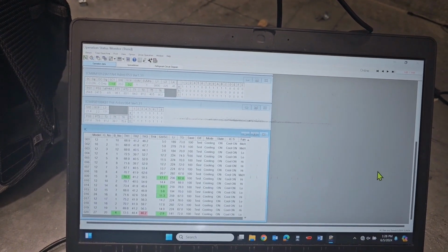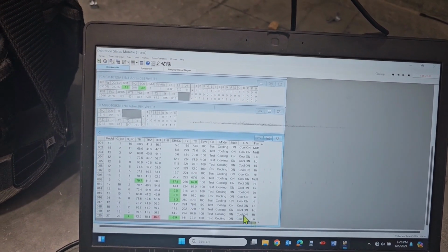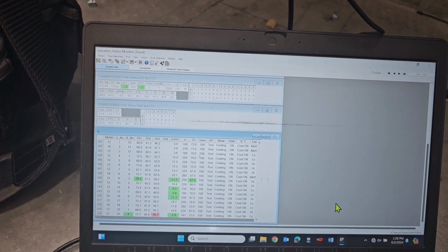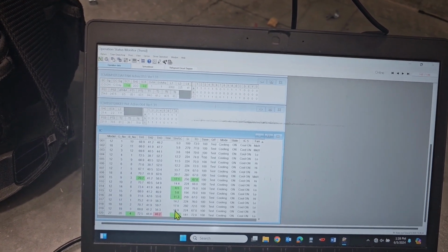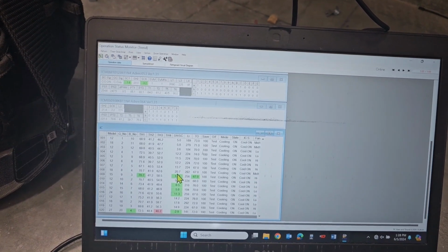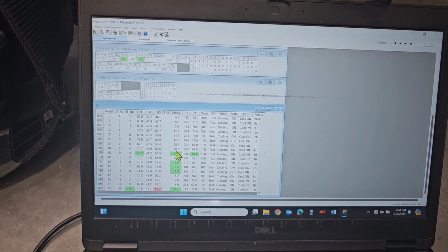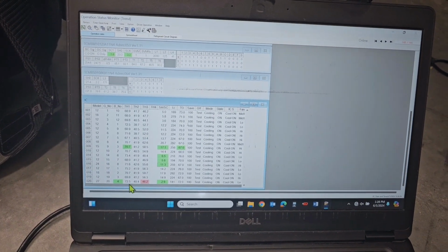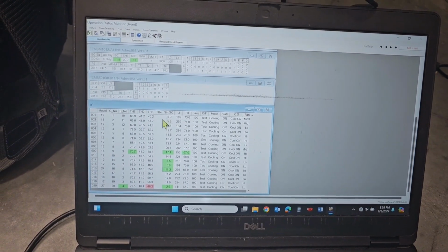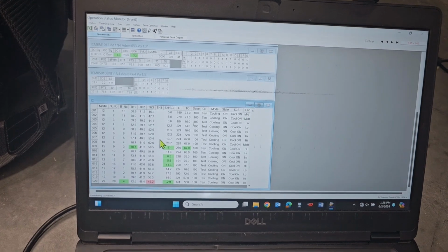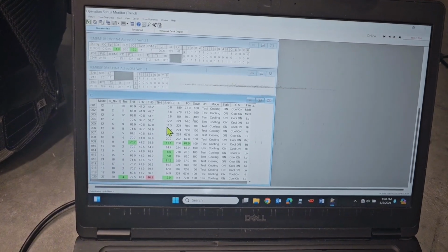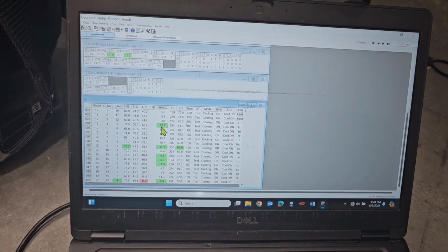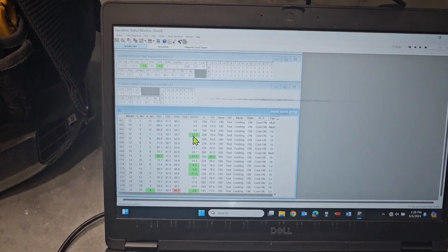But when you open that one valve up and now all of a sudden all of these superheats that were previously 2 to 5 are now in the teens, some are in the 20s, that's pretty telling. Now what you can do to be extra sure is maybe leave everything open and then go close a valve on a system that hasn't given you any problems. So pick one, we can go close this one and see what the system does.